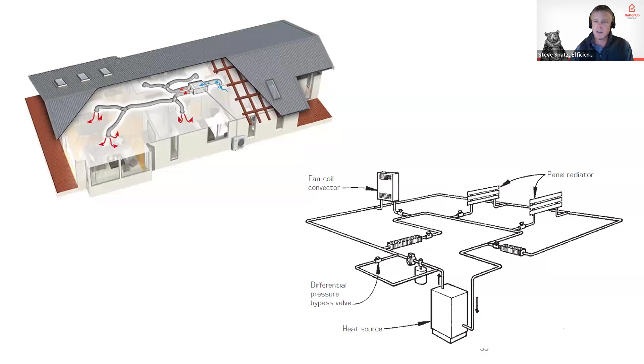So there are specific emitters, as we're calling them here, for distributing that hydronic heating throughout the home that are specific to low temperature water. And these are products that have been available on the market for a long time. But more commonly, what we have in our housing stock in the Northeast, we do have a lot of hydronic heat, but it is designed around higher temperature water. So air-to-water equipment is something you can look at if you're adding on to your home. If you're designing a new home, you can really 100% design a system around using that air-to-water heat pump with low temperature distribution throughout the whole building. In an existing building, though, it does take another layer of evaluation to determine if what you have for distribution in the house is going to be able to work with lower temperature water moving through it. So that is a factor that comes into play with considering air-to-water systems for existing buildings.